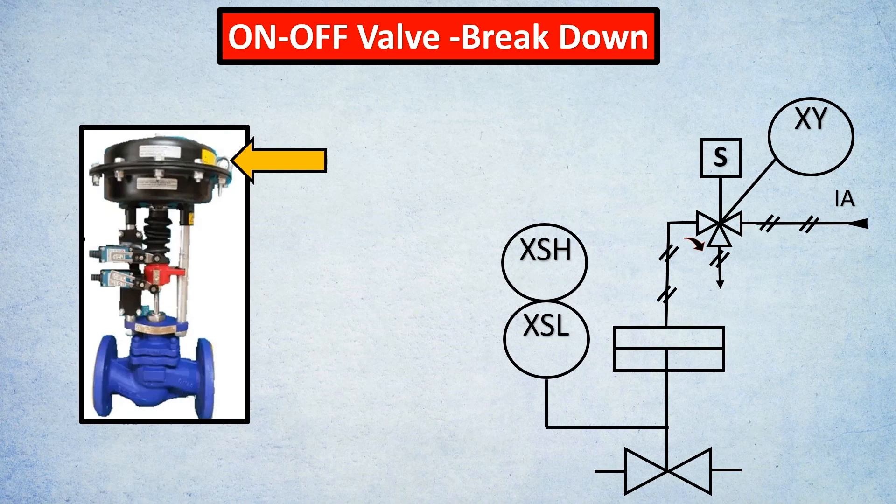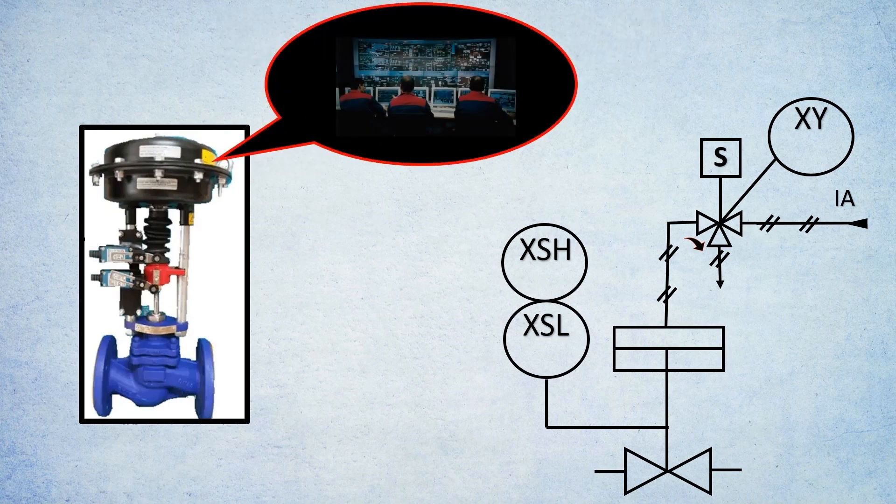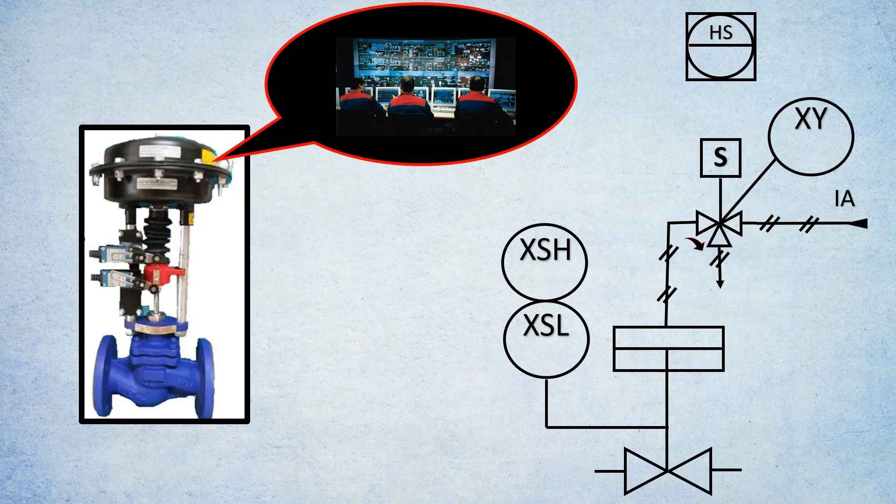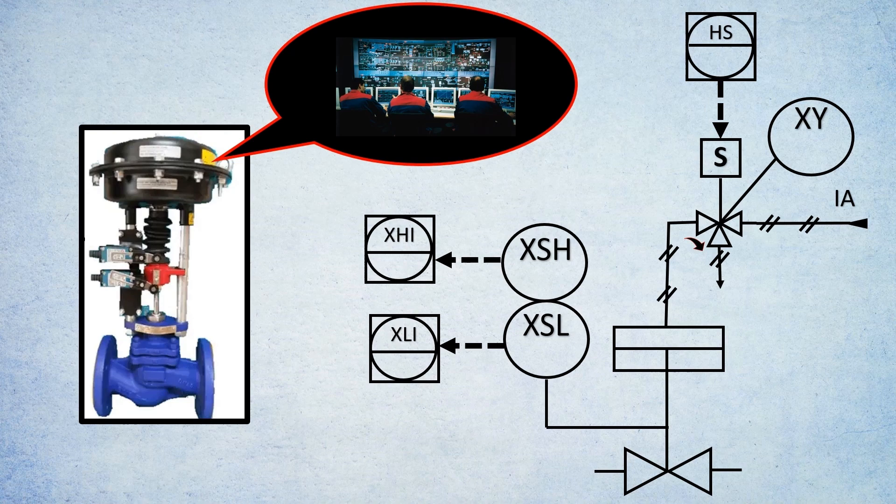So O stands for open and C stands for close. Next, you have the control system. The operator sitting in his cabin gives the first signal, called HS. It's a switch he presses on the control system that activates the solenoid. Then these two limit switches send control signals to the control system, letting the operator know the valve has functioned as indicated. It's feedback to the operator that the intended function is happening.